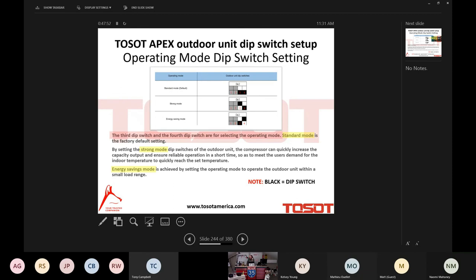Now, the third choice is energy savings, and I caution you here, because my feeling about the energy savings mode is this. If this system was properly sized to begin with, and I got to make some assumptions. Now, you could say that's a bad assumption to make, but I don't care. I have more trust in our trade, right? I want to believe that someone in this process has properly done a heat gain, heat loss calculation and knows that this application requires a 2, a 3, a 4, or a 5, right? And has sized the equipment accordingly and correctly. That's a professional job, my friends, right? That's what professionals do. Discussion for another day. What I am suggesting here is if the system is properly sized and then the energy savings mode is chosen, it's probably not going to hit set point, people, right? You're going to be running at a lower capacity, right?